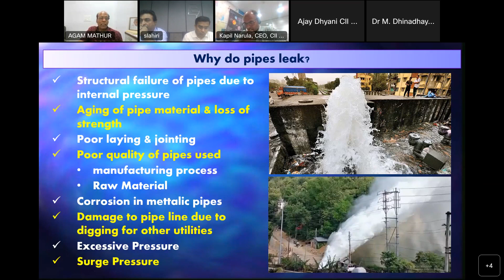Corrosion in metallic pipes. In mild steel pipes with age, if the corrosion protection is not good, in due course of time leakages start happening, and it's very difficult to repair and take shutdowns. Quite often, leakages take place due to damage to the pipeline by digging by other utilities, like fiber cable being laid without permission or proper investigation of the site, where they do horizontal drilling and damage the pipes. Then there is excessive pressure: pipes are designed for a certain pressure, and the operating pressure exceeds it due to over-pumping head or surge pressures. So these are some of the causes of leakage in pipelines.